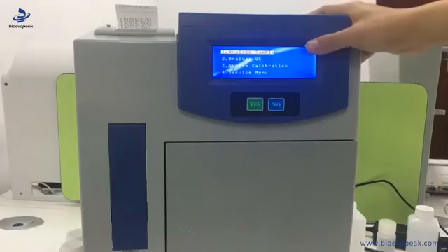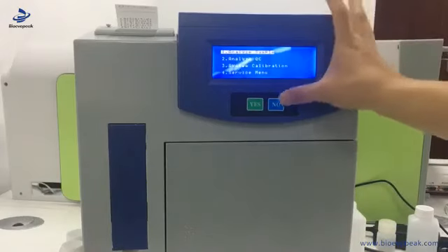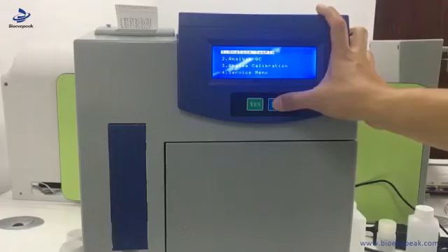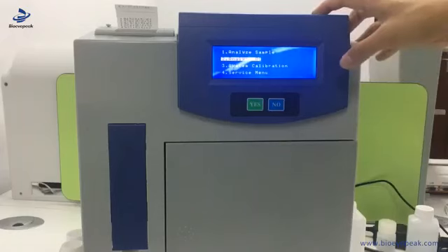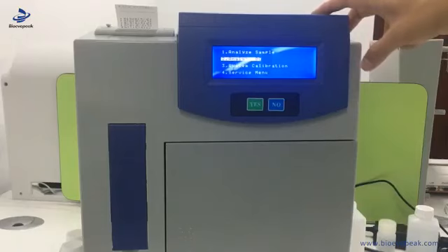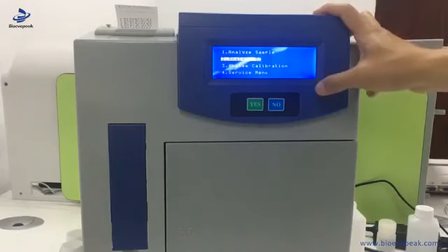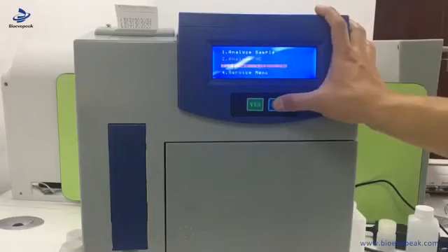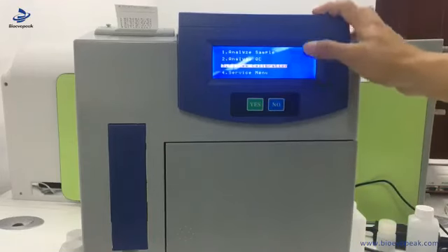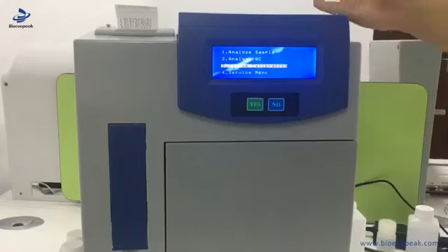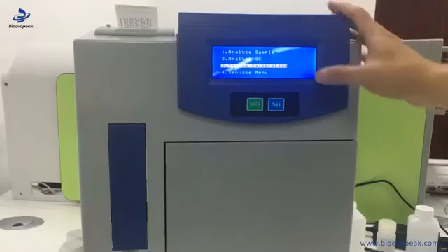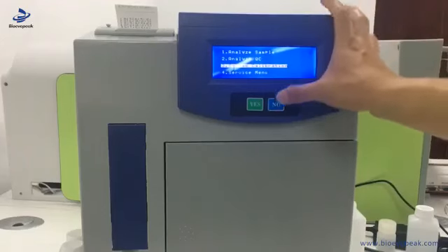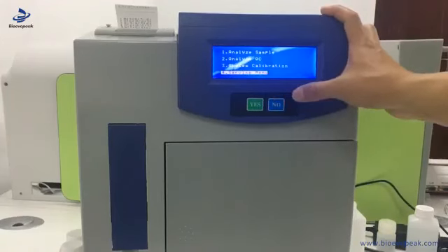So let's go to the first page, and this is sample analysis. It's the first one the end user uses most. We press no. This is analyze QC. When the end user feels the machine is not correct, we use the QC solution to check it. And the third one is system calibration. When the result is not stable or not right, we do the calibration first to make the basis correct. And if you need other services, we go to the fourth menu.